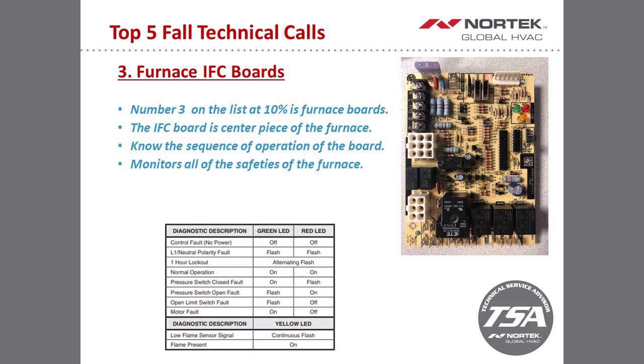So with that, the board will monitor all the safeties in the furnace, and we do have a green and a red LED on the board for troubleshooting. There will be a fault table on the wiring diagram for the furnace. So depending on the fault code that you're getting, you can look at that and see what your fault code is. But there's a green and a red light on there for troubleshooting purposes. They should be solid on, which would be a normal operation, but if you're getting a pressure switch or a limit fault, you'll get that on the green and red light LED.